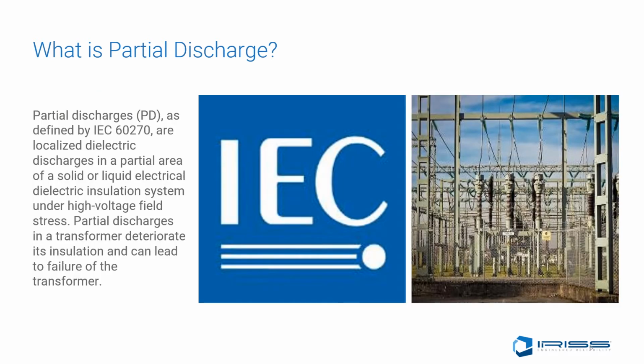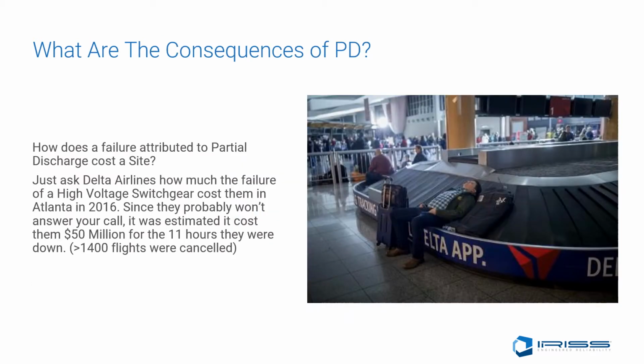Partial discharge, known as PD, as defined by IEC 60270, are localized dielectric discharges in a partial area of a solid or liquid electrical dielectric insulation system under high voltage field stress. Partial discharges in a transformer deteriorate its insulation and can lead to failure of the transformer. So what are the consequences of PD? Well, how does a failure attributed to partial discharge cost at a site?